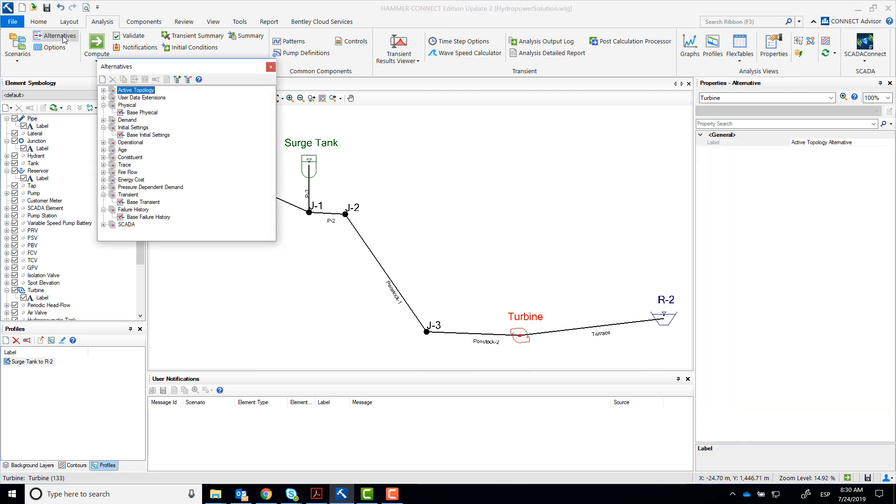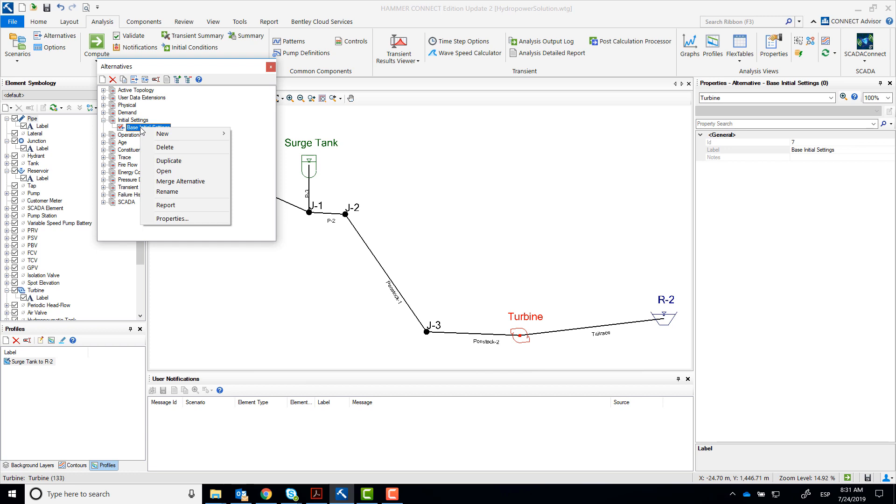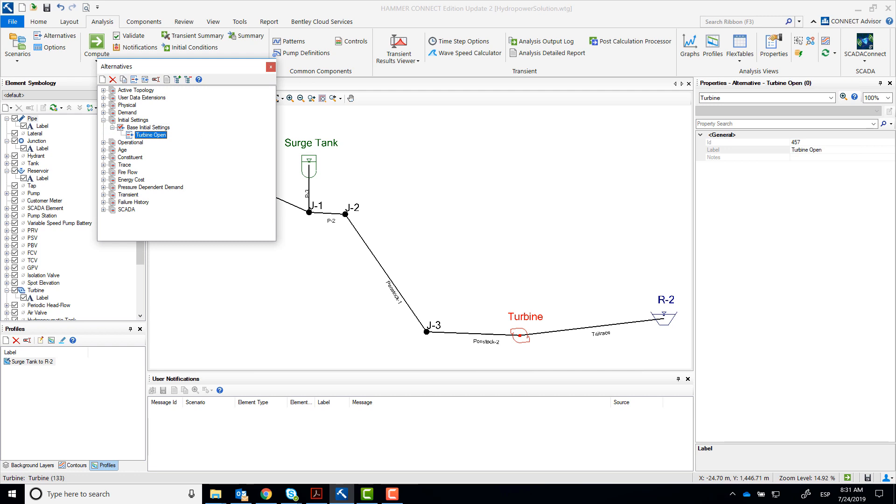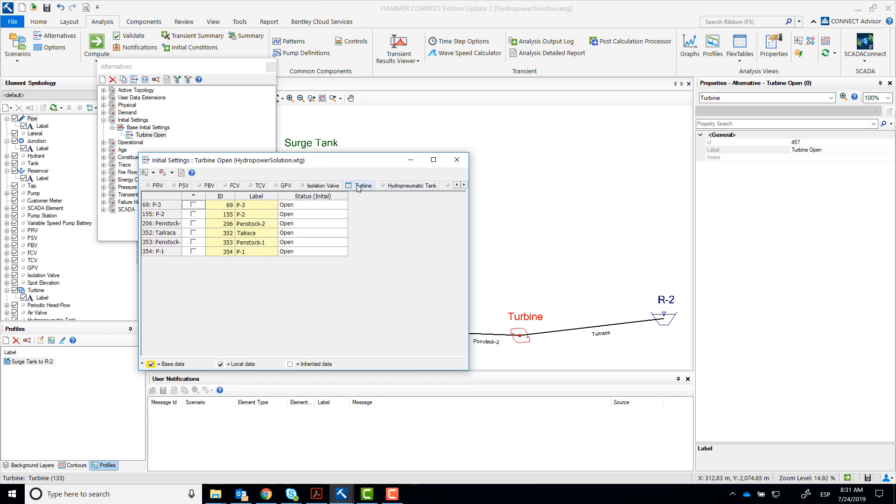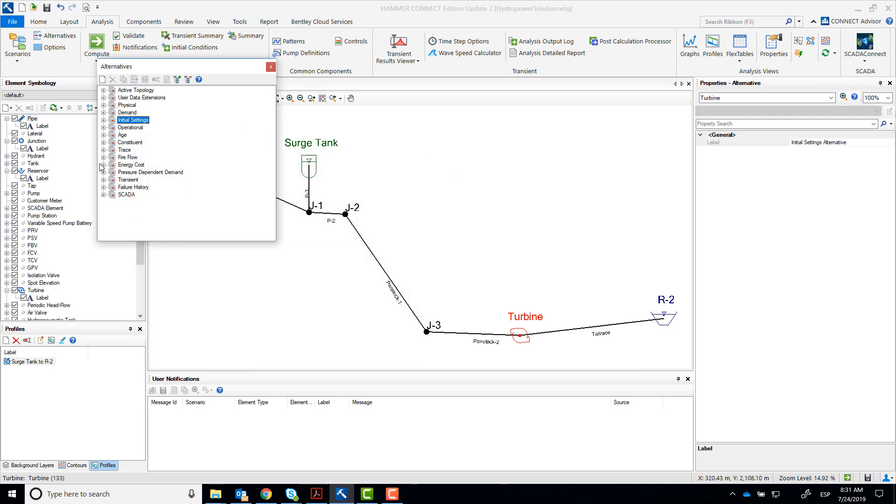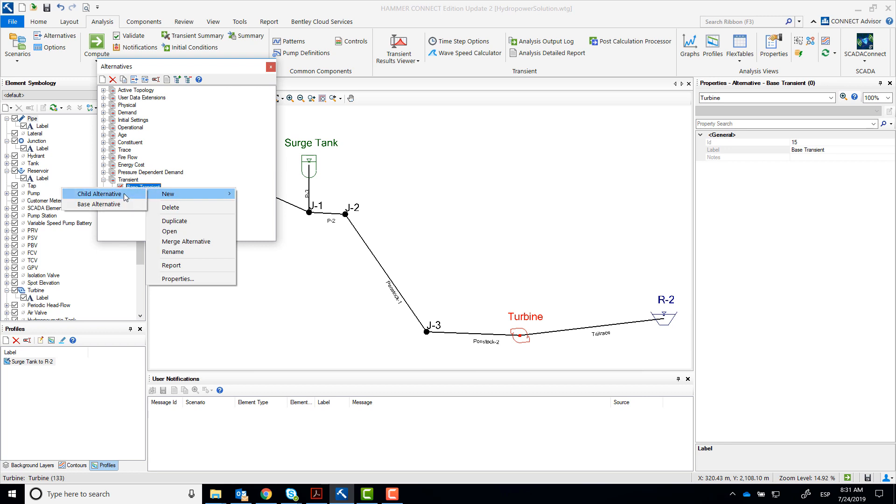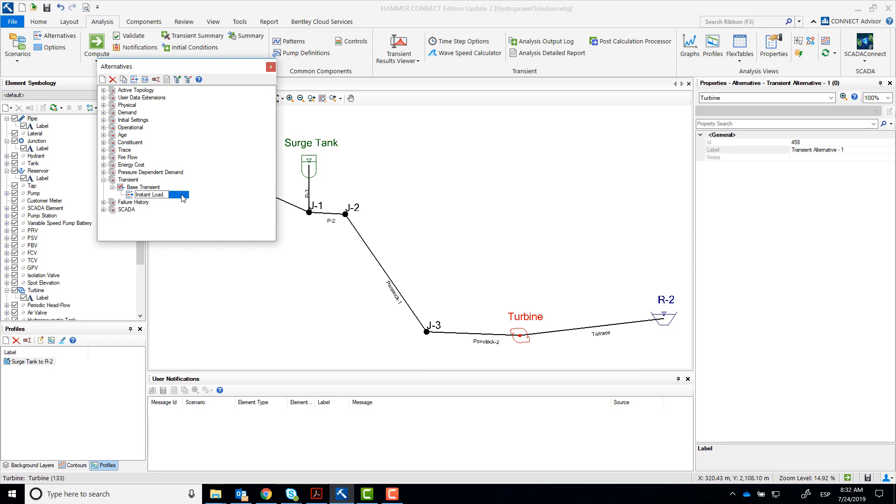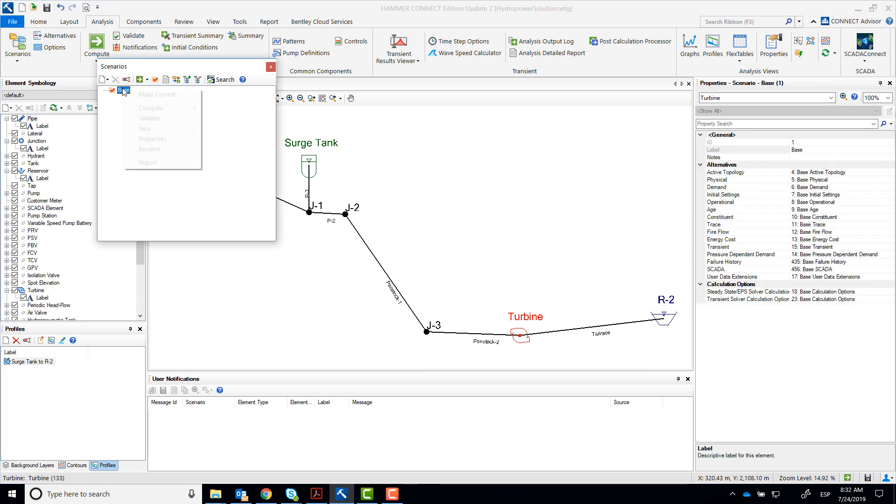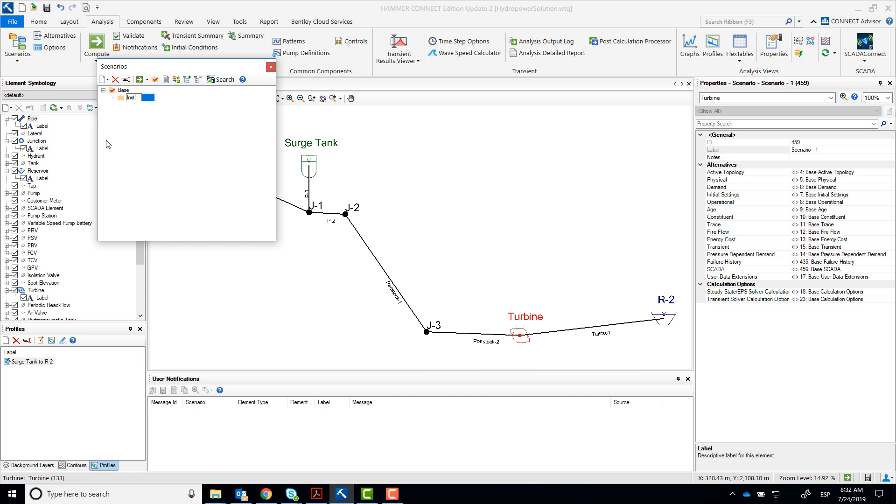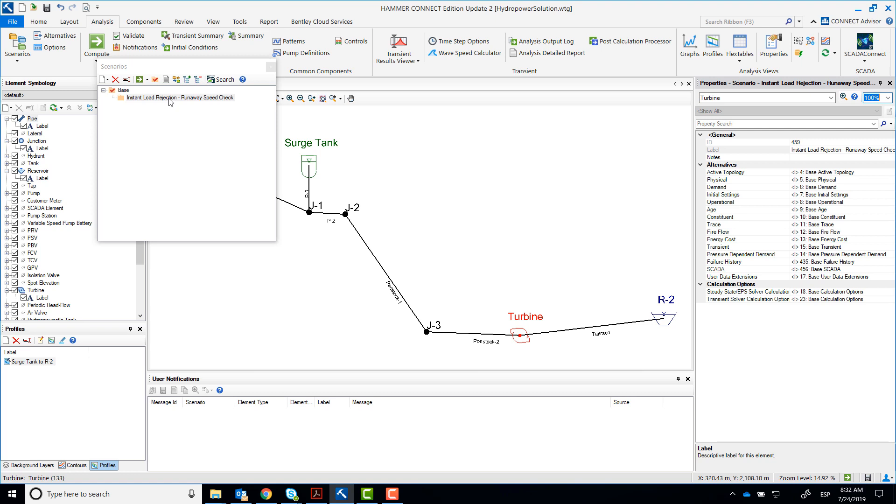We'll start by creating the first scenario, the runaway speed check. The objective of this run is to determine the maximum speed reached by the turbine when the electrical load in the turbine drops instantaneously to zero. Create an initial settings alternative for turbine open and a new transient child alternative which will be called instant load rejection. Make sure that you assign those alternatives to the new scenario.